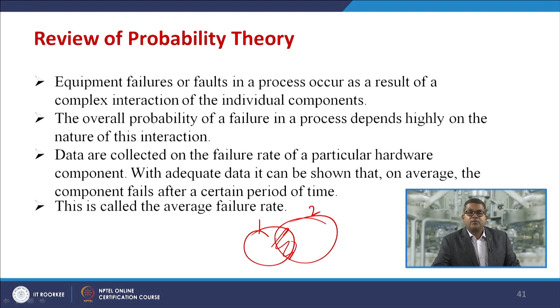Now, data are collected on the failure rate of a particular hardware component. With adequate data, it can be shown that on average the component fails after a certain period of time, and this is called the average failure rate. Now, there are revealed and unrevealed failures. In many chemical processes, it is possible for a piece of equipment to fail without the operator being aware of the situation, and that is called an unrevealed failure. Without regular and reliable equipment testing, the equipment can fail without notice. The failures that are immediately obvious are called revealed failures. So, we must know these types of approaches.